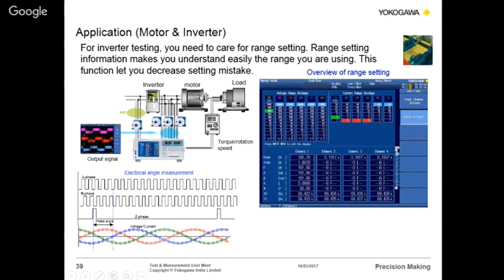Okay, and the motor efficiency can be calculated by mechanical output divided by three-phase electrical input. And the total efficiency is the mechanical output divided by the single phase input, which includes the inverter and the motor. So at a different load, maybe 50% or 100% or 75%, whatever it is, the readings are voltage, current, power factor, phase angle, frequencies and all those things, and the efficiency, again with respect to elements 1, 2, 3, 4.